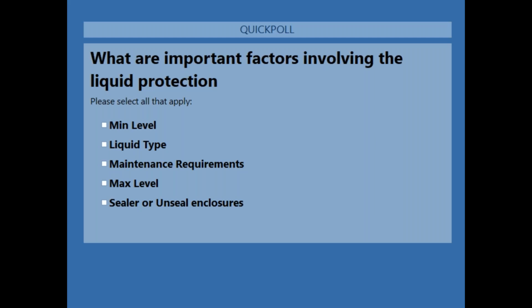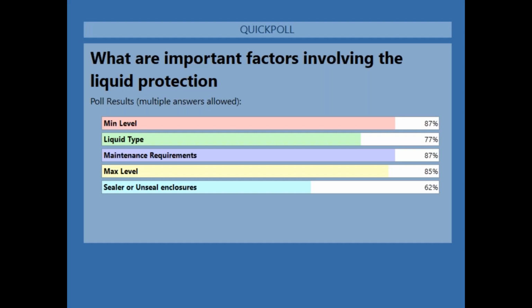I think this one has people unsure. 60% voted, we'll close it now. So the correct answer is all of those. You need to know the minimum and maximum levels that are allowed. You need to know what liquid type, because you can't just replace it with whatever you want. You need to follow the maintenance requirements, and you need to know if it's a sealed or unsealed enclosure. A sealed enclosure you cannot open. An unsealed enclosure you cannot open unless you follow the IOMs. Follow the manufacturer's instructions and the certificate and the standard.